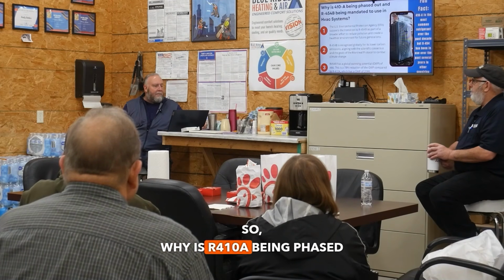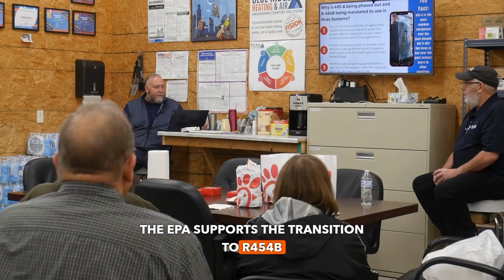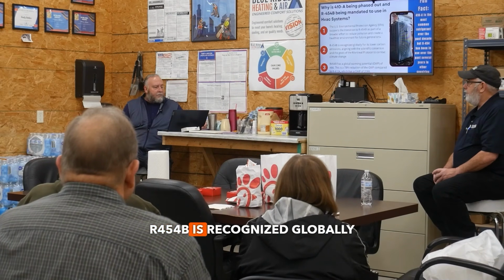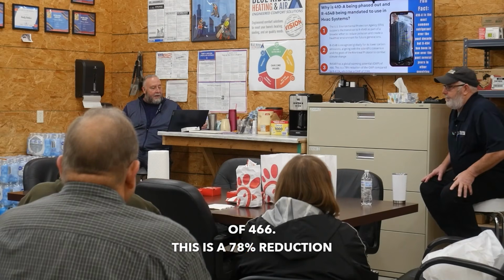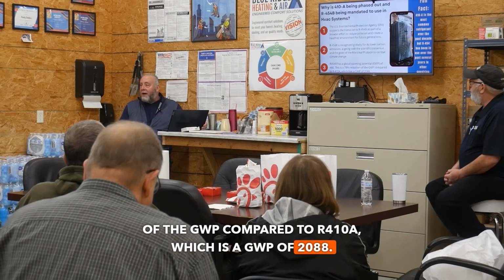So why is 410A being phased out and R454B being mandated for the new systems? Well, the EPA supports the transition to R454B as part of a broader effort to reduce pollution and create a healthier environment for our future generations. R454B is recognized globally for its lower carbon emissions, aligning with the scientific consensus and the goals of the Montreal Protocol to combat climate change. R454B has a global warming potential, or GWP, of 466. This is a 78% reduction compared to R410A, which has a GWP of 2,088.